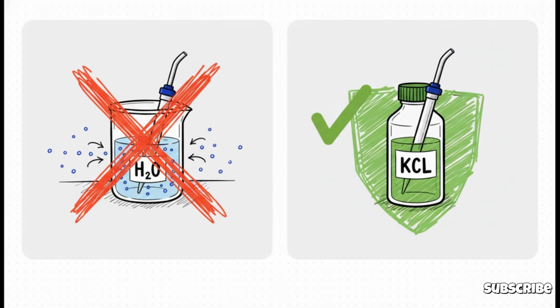All right, listen up, because if there's only one thing you remember from this entire explainer, I want it to be this. Are you ready? Never, ever, ever store your pH probe in distilled or deionized water. It is the absolute fastest way to kill it, period. Why? Well, it's just basic osmosis, right? The inside of your probe is filled with this very specific salt solution. When you stick it in pure water, all those essential salts start leaching out of the probe, trying to balance the concentration. You are literally bleeding the life out of your probe. You have to use the proper storage solution. It's specifically designed to keep the probe's internal chemistry perfectly happy and stable.